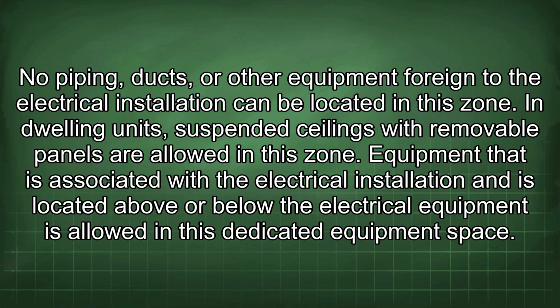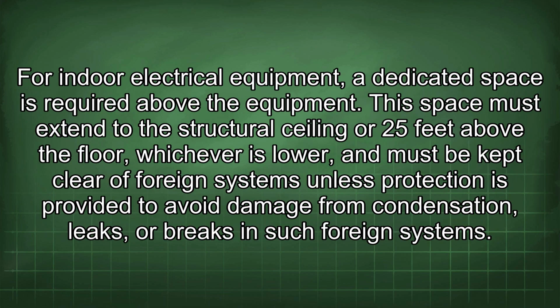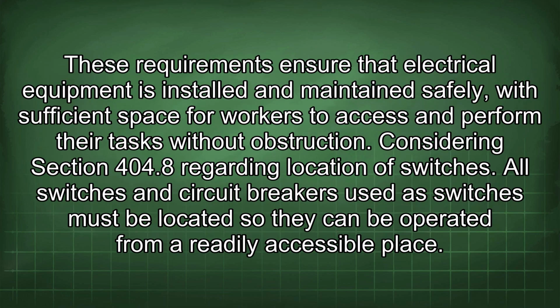Equipment that is associated with the electrical installation and is located above or below the electrical equipment is allowed in this dedicated equipment space. For indoor electrical equipment, a dedicated space is required above the equipment. This space must extend to the structural ceiling or 25 feet above the floor, whichever is lower, and must be kept clear of foreign systems unless protection is provided to avoid damage from condensation, leaks, or breaks in such foreign systems. These requirements ensure that electrical equipment is installed and maintained safely, with sufficient space for workers to access and perform their tasks without obstruction.